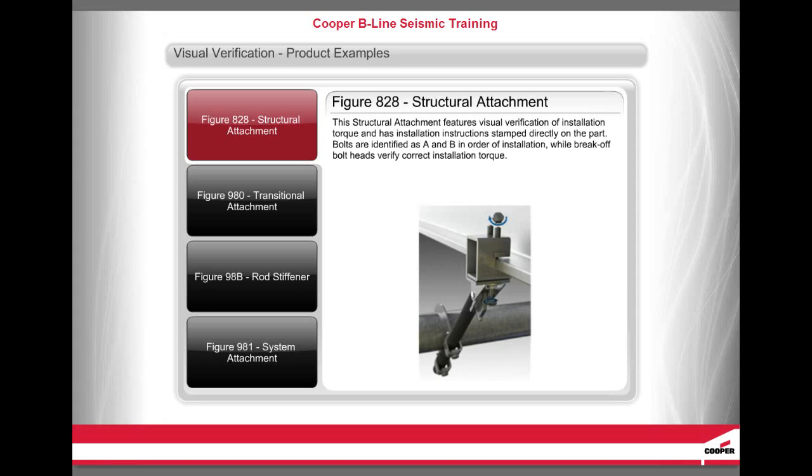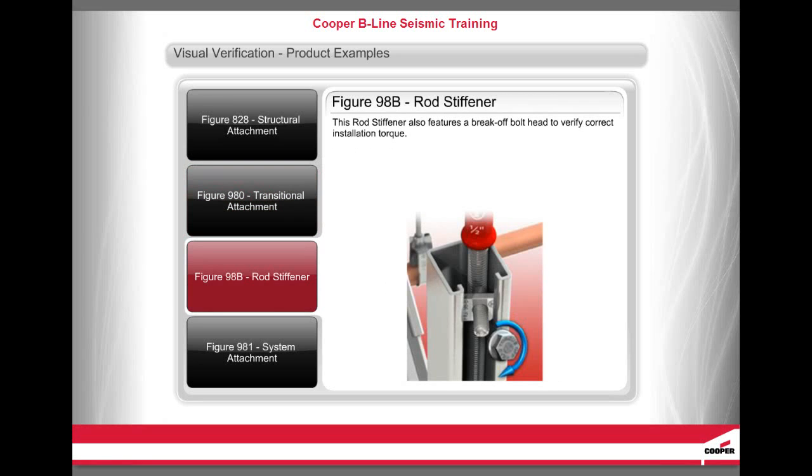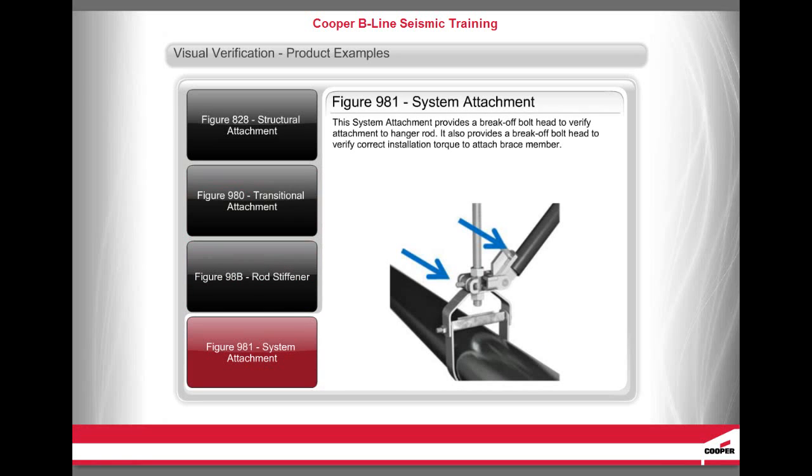Cooper B-Line offers many products with visual verification features — all Cooper B-Line seismic products have some type of visual verification, most typically break-off bolt heads or nuts. This structural attachment features visual verification of installation torque and has installation instructions stamped directly on the part; bolts are identified as A and B in order of installation, while break-off bolt heads verify correct installation torque. This transitional attachment offers visual verification of proper engagement of channel or brace pipe with a break-off bolt head to verify correct installation torque. This rod stiffener also features a break-off bolt head, and this system attachment provides a break-off bolt head to verify attachment to the hanger rod and correct installation torque for the brace member.